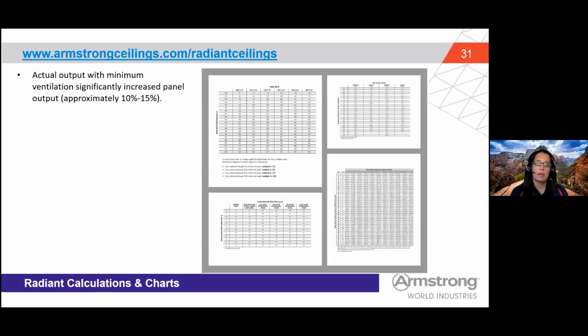As I mentioned, on our website at armstrongceilings.com/radiantceilings, we have example calculations for each of these solutions, whether it's perimeter or full ceiling, along with our performance charts. So if you know your mean water temperature and room design, you can back into these to see what size is required and how many passes you would need. Keep in mind these performance charts show actual output with minimum ventilation; significant airflow increases the panel output. So these are worst case, assuming no natural convection, no airflow—you'll see an additional 10 to 15%.